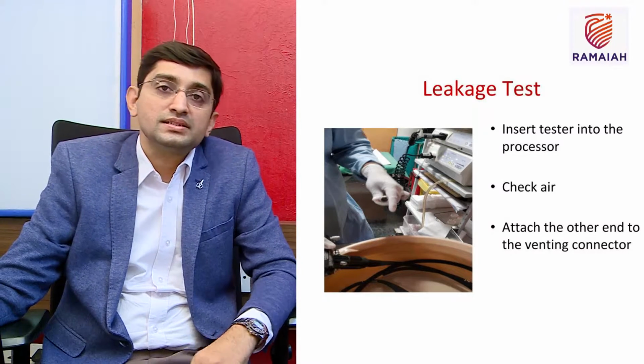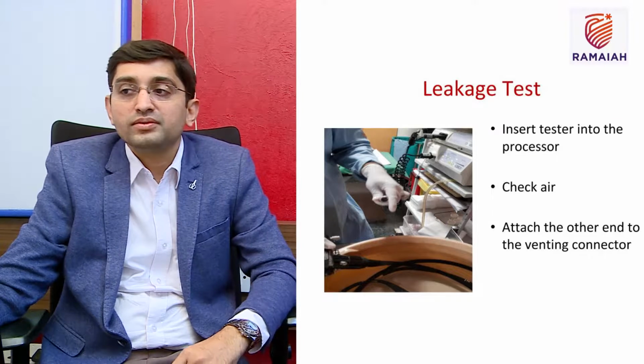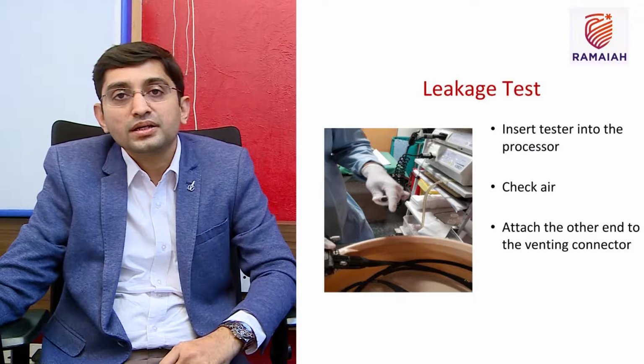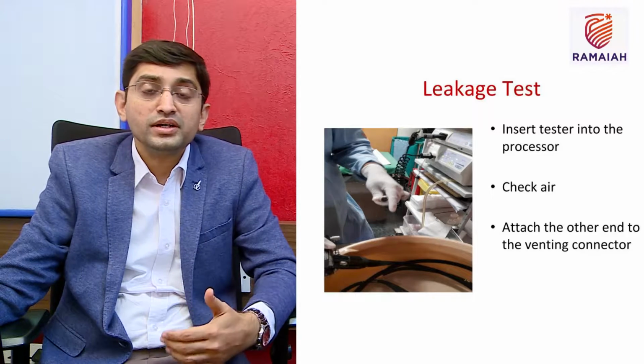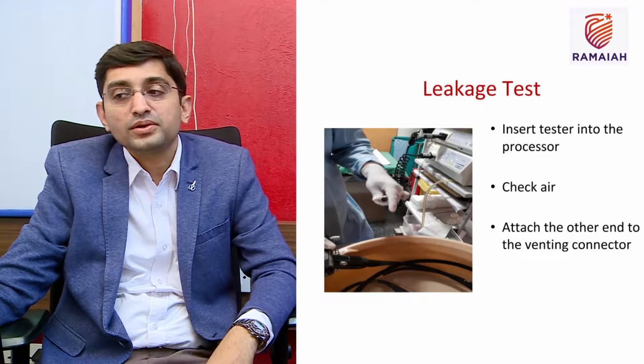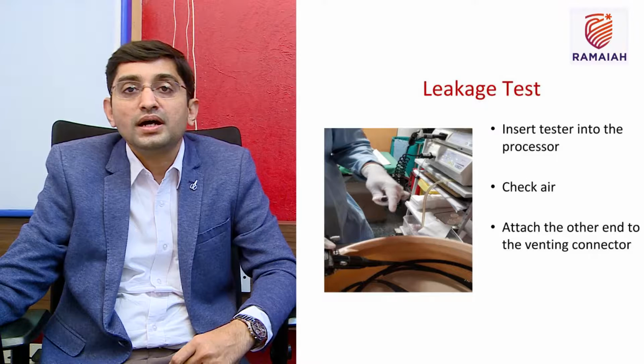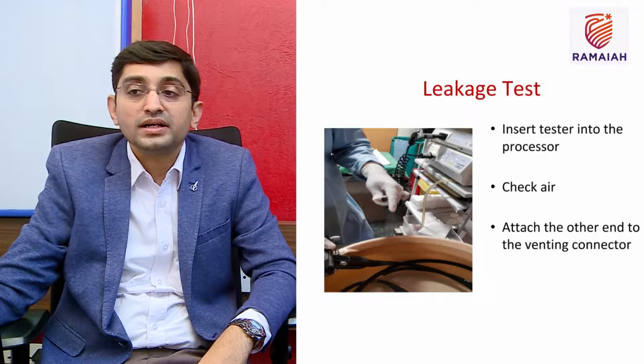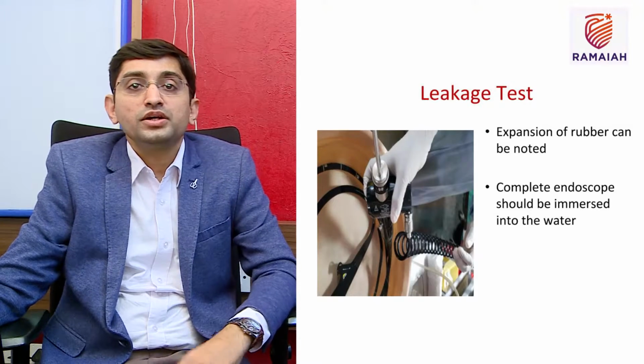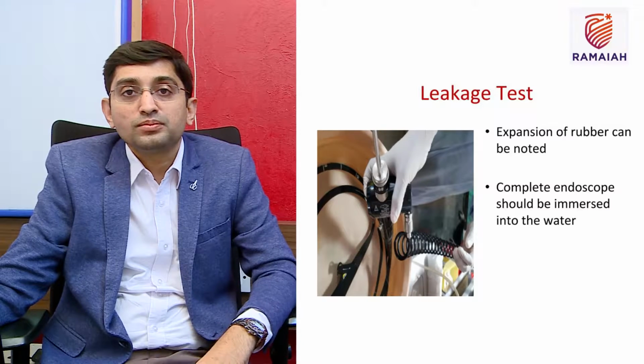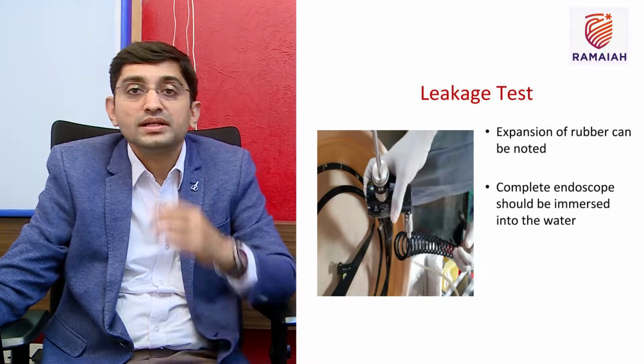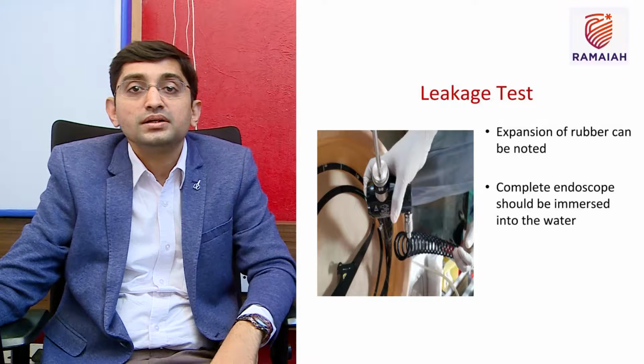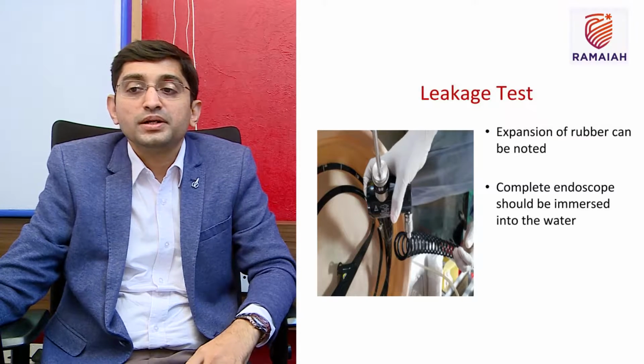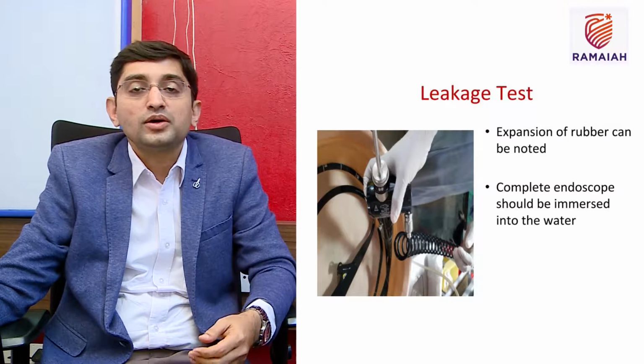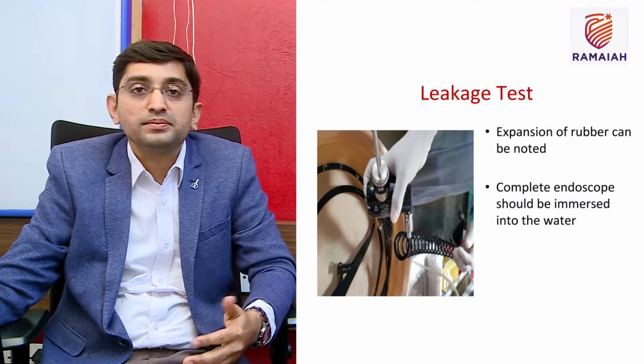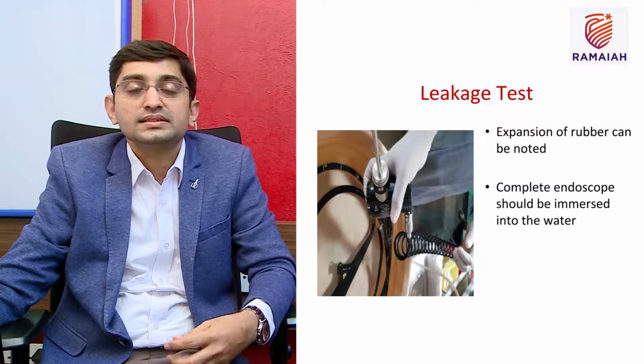Leakage testing is done by a leakage tester, whose proximal part is connected to the processor, and we check the air that is coming from the processor. We connect the other end of the leakage tester to the venting connector of the scope. Then we immerse the complete scope within the water and see whether there is any expansion of the rubber at the tip of the scope. That is very important, because if we see expansion of the rubber from outside, that means there is some leakage happening.